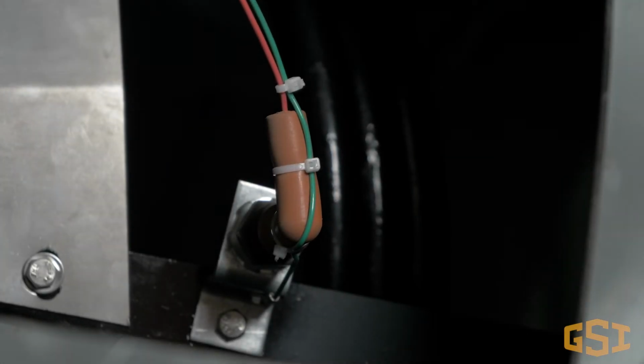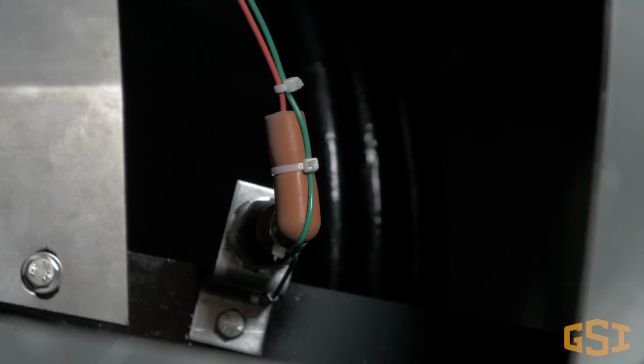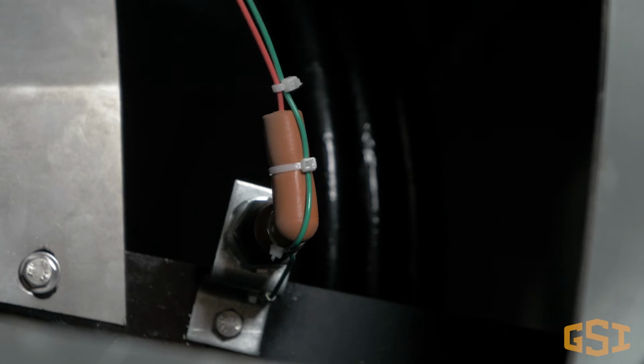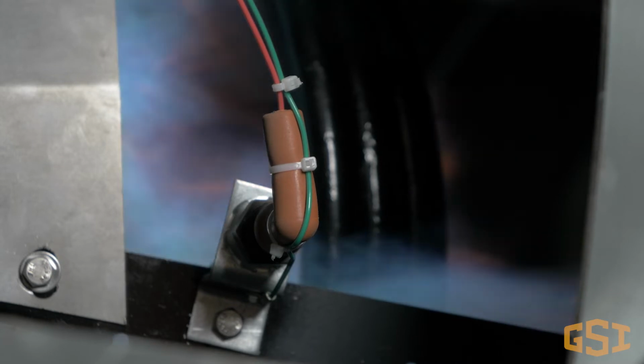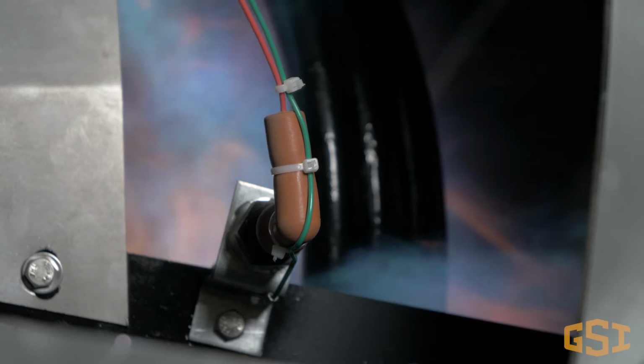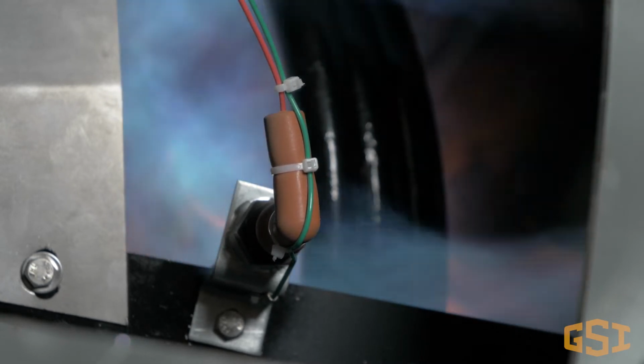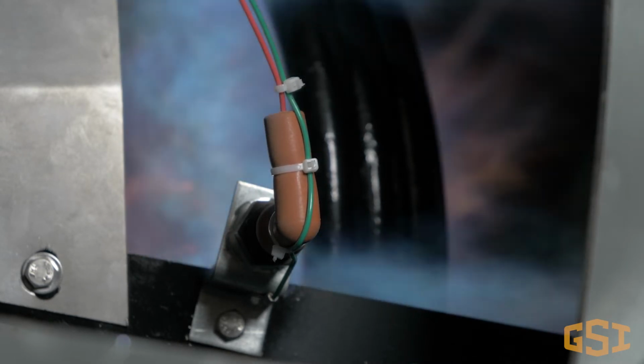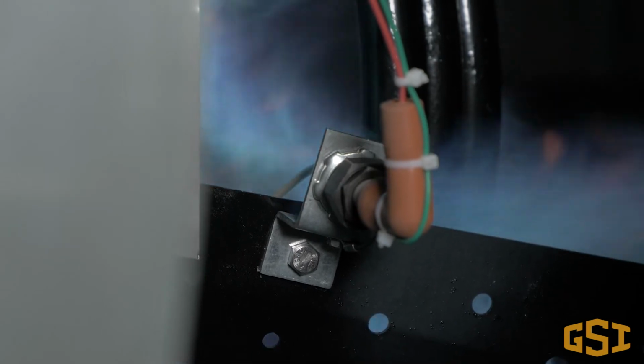Before we begin the actual troubleshooting process, let's take a minute to better understand the process of using flame rectification for flame detection. What is flame rectification? Flame rectification is an electrical process that causes a low-level DC current to be conducted from the flame rod through the flame and back to ground. The current traveling through the flame is detected by a flame control module, which informs the ignition control system if flame is present. So, what causes a dryer to shut down with loss of flame error?